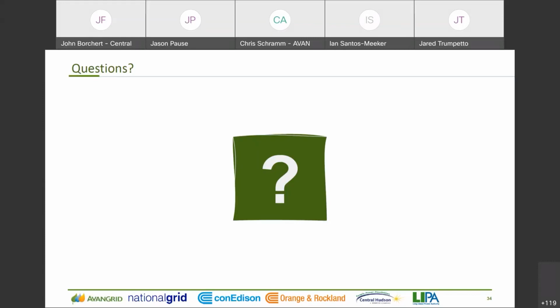Sure. At Avangrid at least, and I'm fairly sure this is consistent across New York utilities, we use PSSE, a Siemens power flow software, usually used for base case setup and visualization of power flow. We also use PowerGEM's TARA for rapid contingency analysis, since we run hundreds or thousands of faults at once. We also use tools like ASPEN's OneLiner for short circuit analysis and other protection and controls analysis. I'm not sure if other utilities use other software I'm not mentioning here.